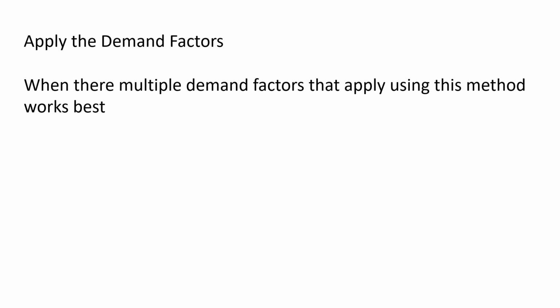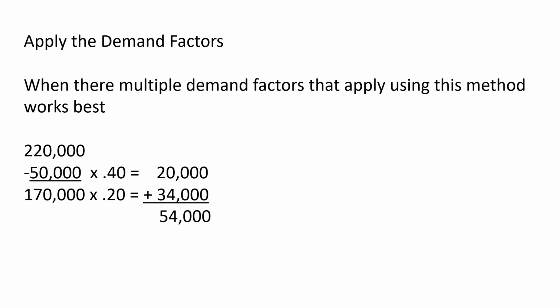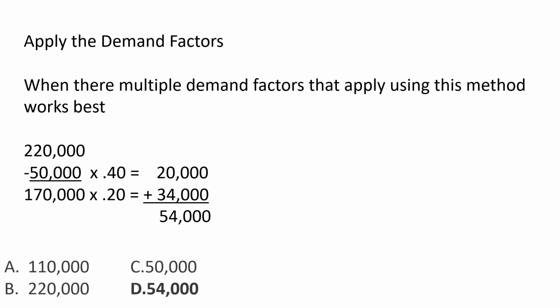So we have to be careful that we structure this question a little bit differently because there are multiple demand factors. When you're doing multiple demand factors, this method works every single time. First, you list your total VAs, and then you set up your math problem. You minus the 50,000 and set it up to give you your other total. Then going across, you multiply the first number by its demand factor. In this case, 40%, it'll be 0.40. That gives us 20,000 VAs. Then the remainder, you multiply by 0.20, and that gives you 34,000 VAs. You add them together, you have 54,000 VAs, and you select D.